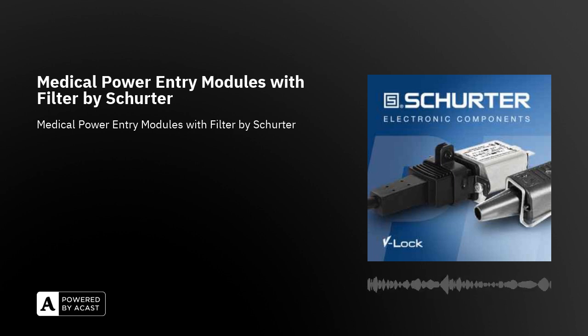Home care medical equipment. The requirement according to IEC 60601-1-11 is protection class 2, double insulation, test voltage of 4000 volts between LN and the filter case, and minimum protection against water IP21. The solution provided by Schurter is a PEM with C8 or C18 inlet connectors without PE, reinforced insulation inside of the filter, 8 mm surface and air distances between live parts and the filter housing. PEM will withstand a test voltage greater than 4000 volts DC between LN and the filter housing.